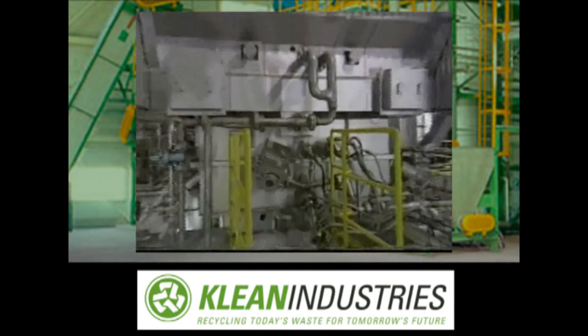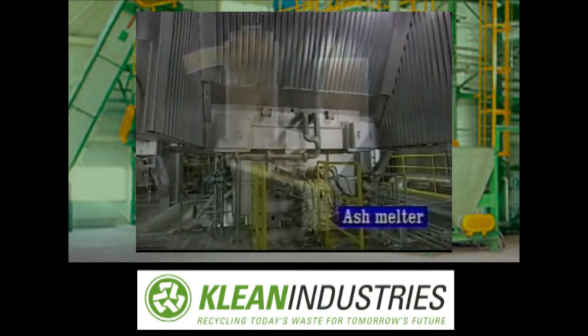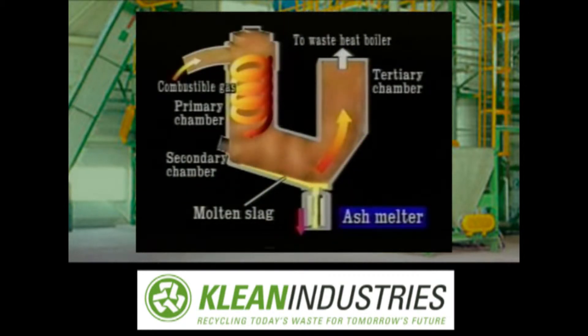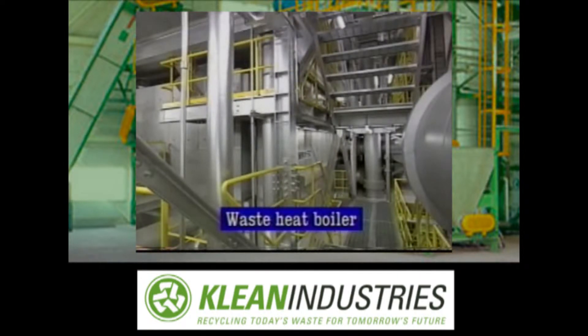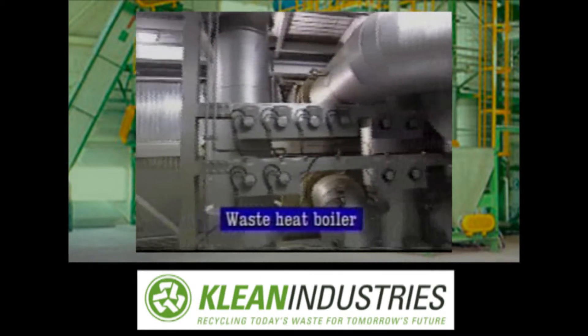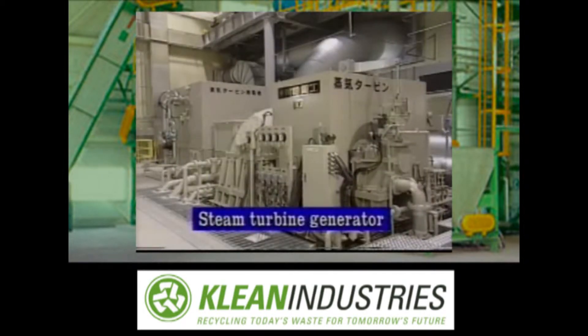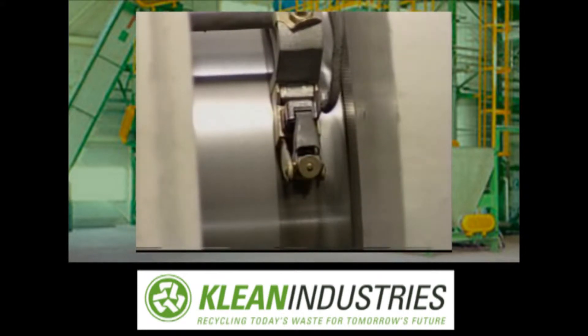The gas, stripped of slag, is completely combusted at 1,350 degrees Celsius. The waste heat boiler effectively recovers heat energy involved in the flue gas and utilizes the heat to generate steam. The temperature of the flue gas at the inlet of the waste heat boiler is higher than 1,200 degrees Celsius. The generated steam is utilized for the center's steam turbine to generate electricity, reaching a maximum of 12,000 kilowatts — enough for consumption in the entire center. Surplus electricity is sold to electric power companies.